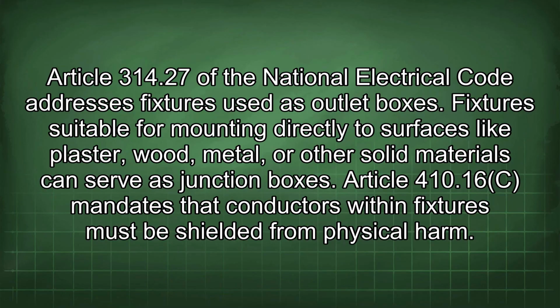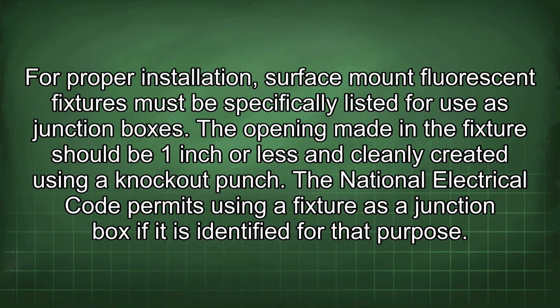314.27 of the National Electrical Code addresses fixtures used as outlet boxes. Fixtures suitable for mounting directly to surfaces like plaster, wood, metal, or other solid materials can serve as junction boxes. Article 410.16(C) mandates that conductors within fixtures must be shielded from physical harm. For proper installation, surface mount fluorescent fixtures must be specifically listed for use as junction boxes.